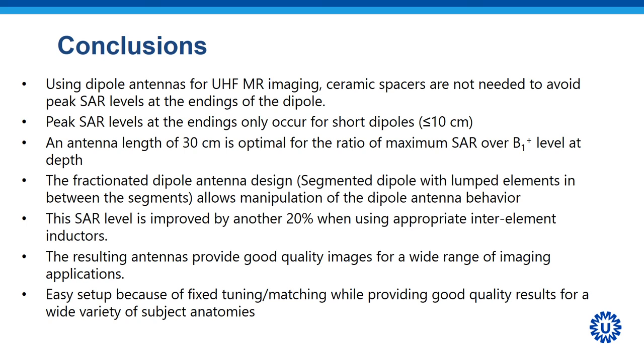For example, the SAR level can be improved by another 20% when using appropriate inter-element inductors. The resulting fractionated dipole antenna design provides good quality images for a wide range of imaging applications. The easy setup with fixed tuning and matching still provides good quality results for a wide variety of subject anatomies.